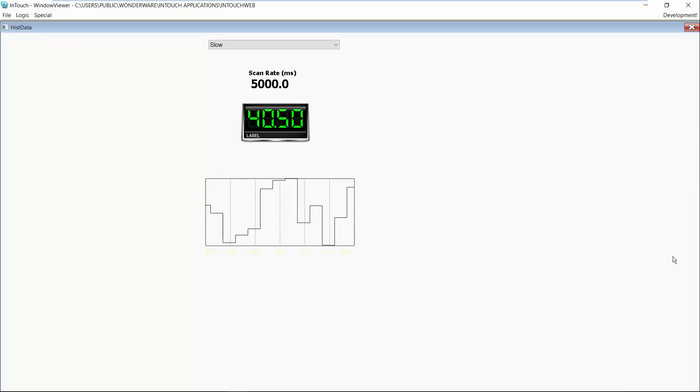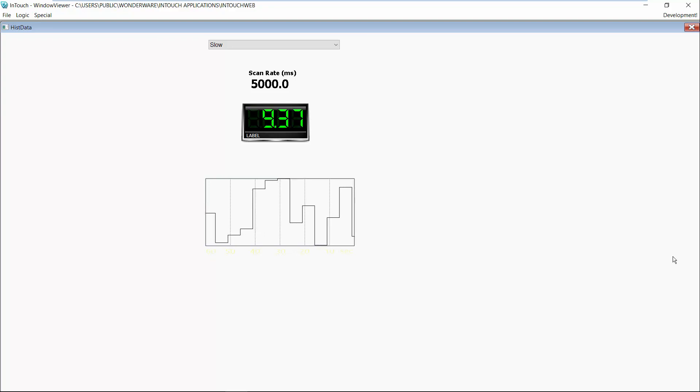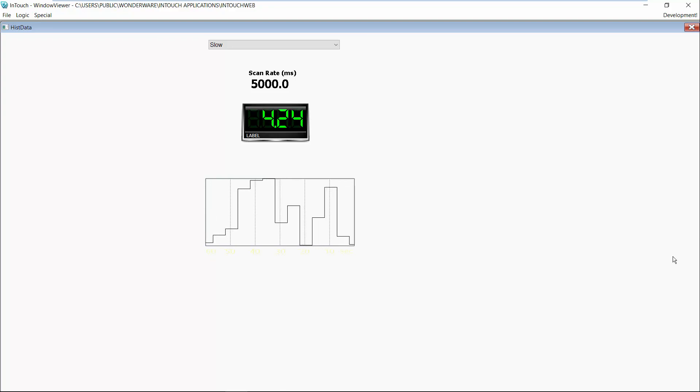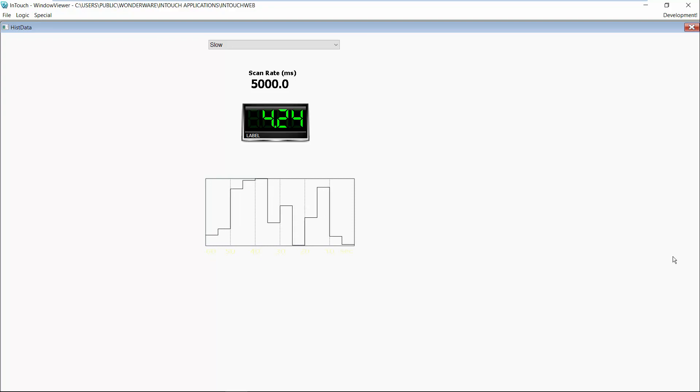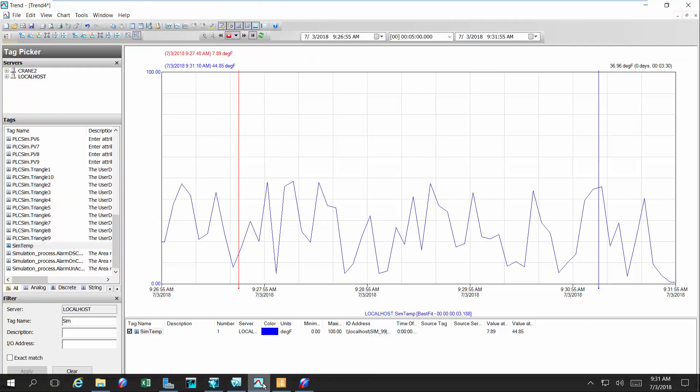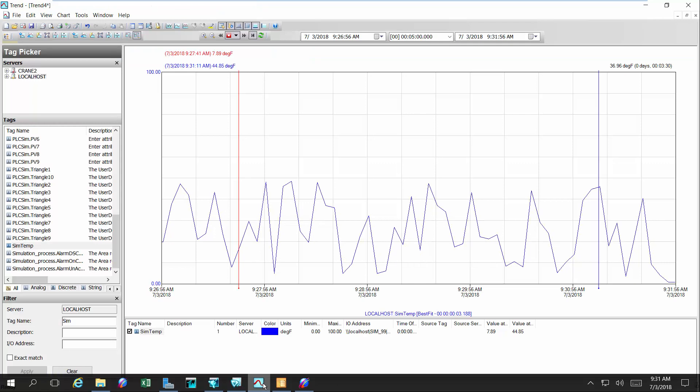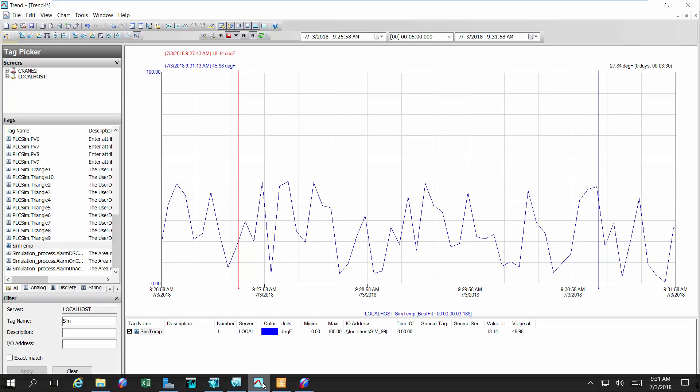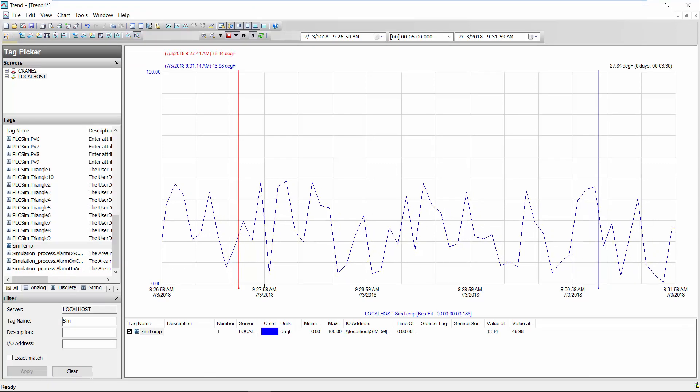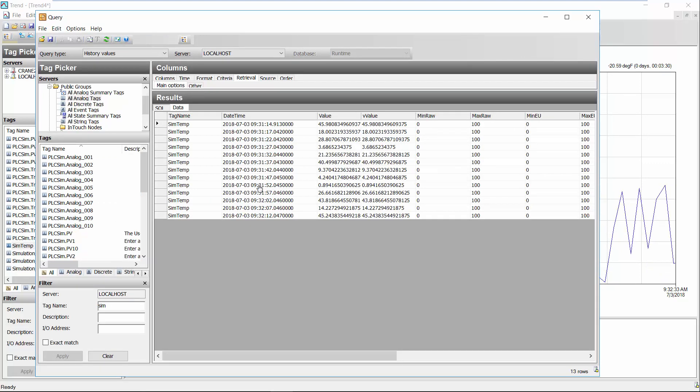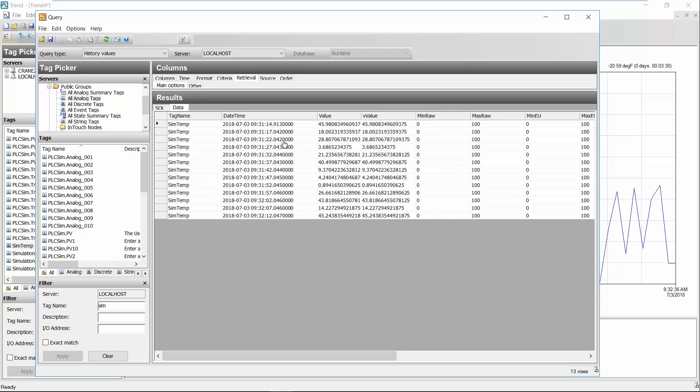If you look at my InTouch screen here you can see you have some data being pulled at a five second rate. You can see the refresh on the screen is five seconds. You can see our thumbnail of our graphic is being updated every five seconds. We consider this a slow pull mode. If I want to look at this in a trend I can see this data being logged to my historian at that frequency. If I look at the data in my historian query tool we can see the data is indeed being updated every five seconds.